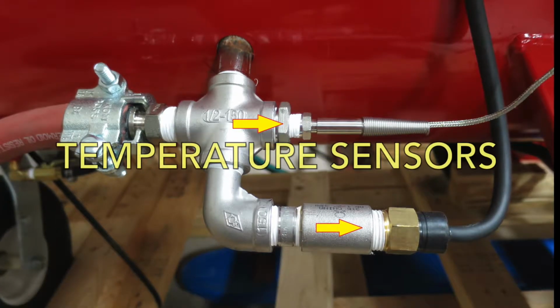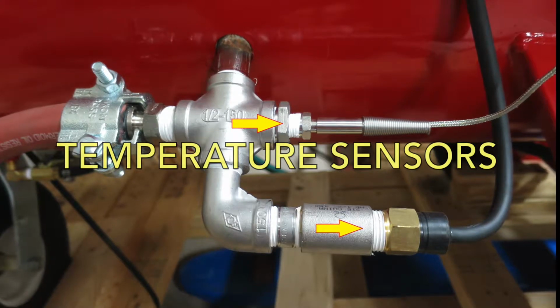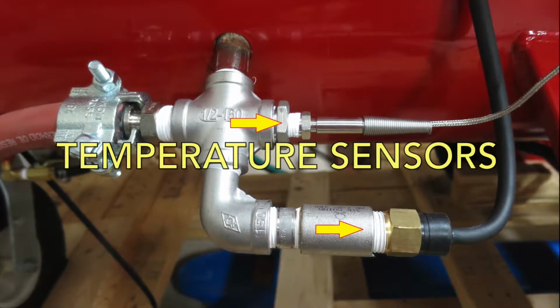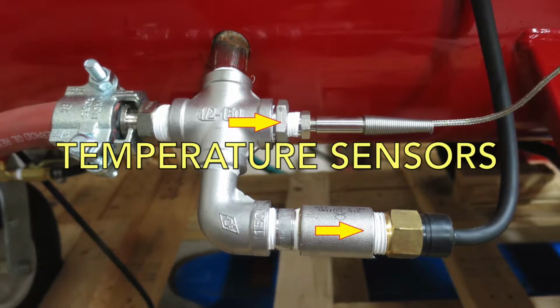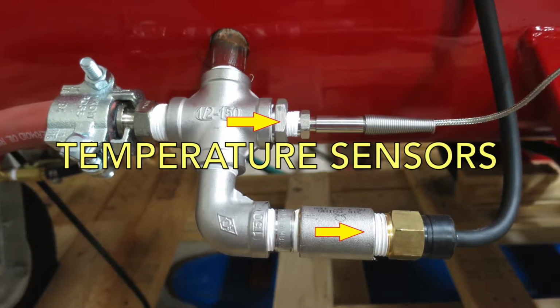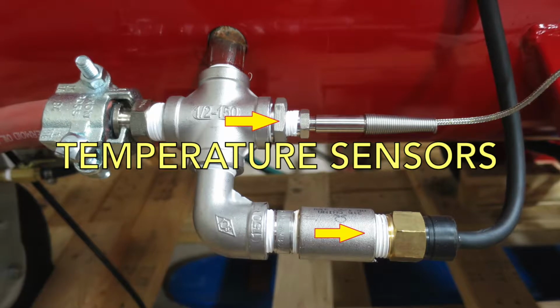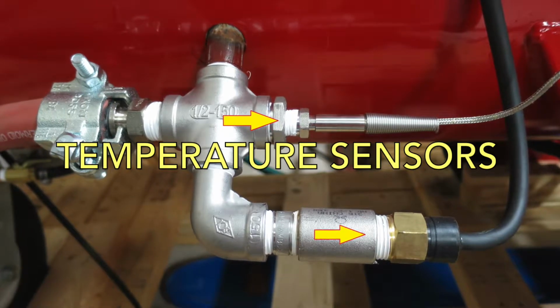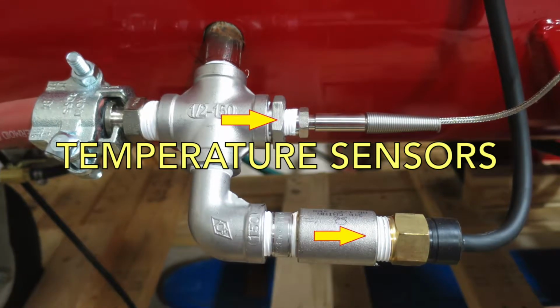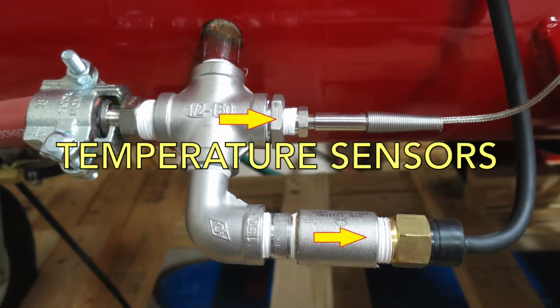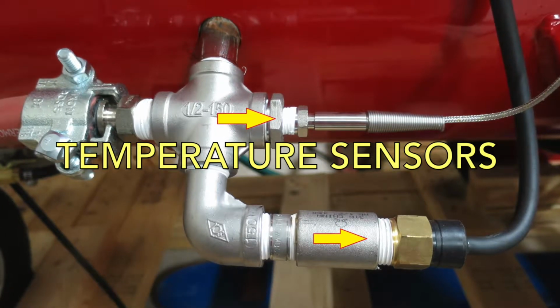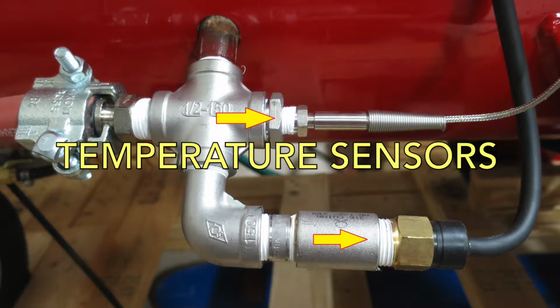The temperature of the water steam mixture is monitored as it comes out of the burner coil and goes into the wand hose. The temperature is displayed in Celsius on the front panel meter. The over temperature shutdown sensor has a black wire attached to it and protects the equipment from getting too hot. It will automatically turn off power to the burner at approximately 175 degrees Celsius.